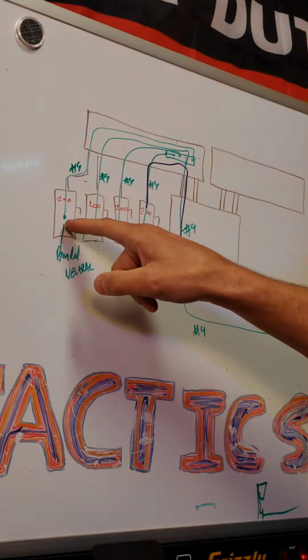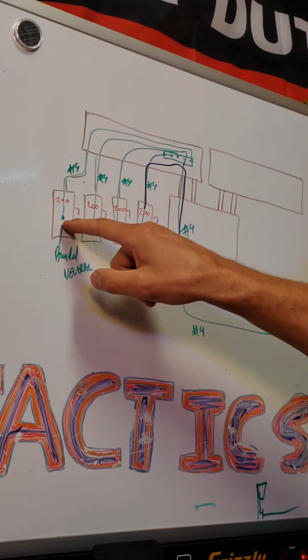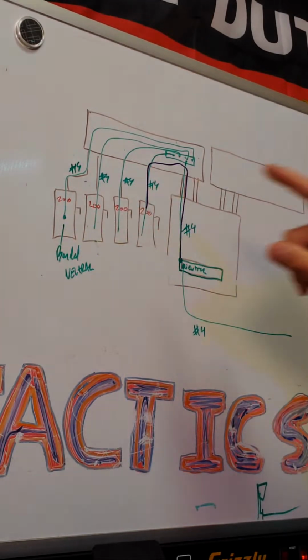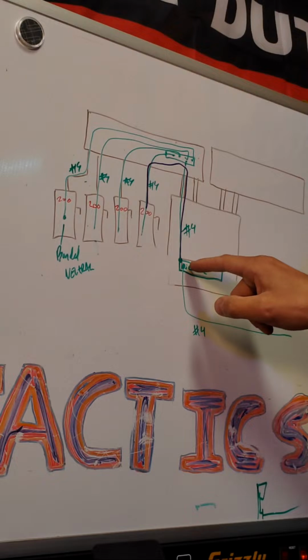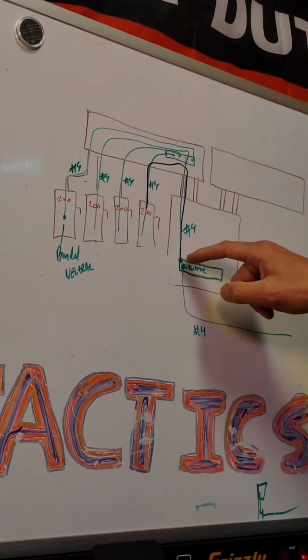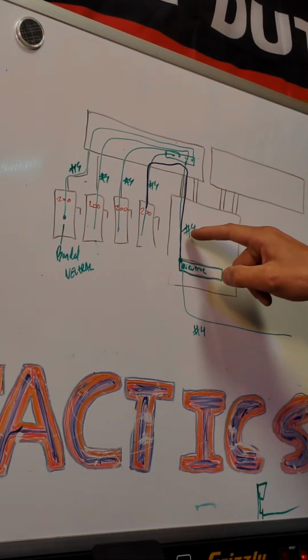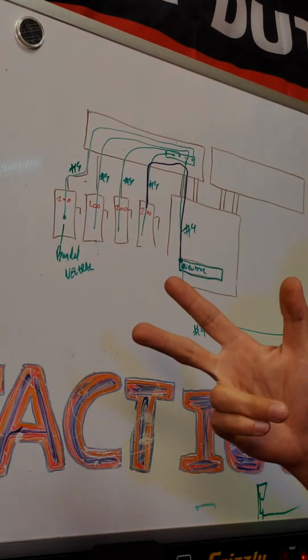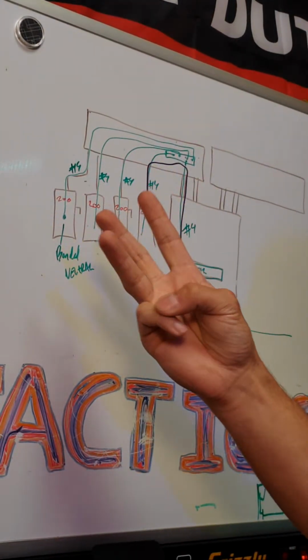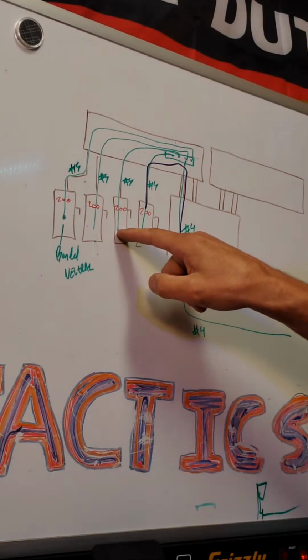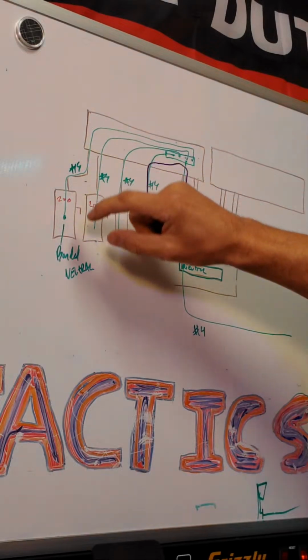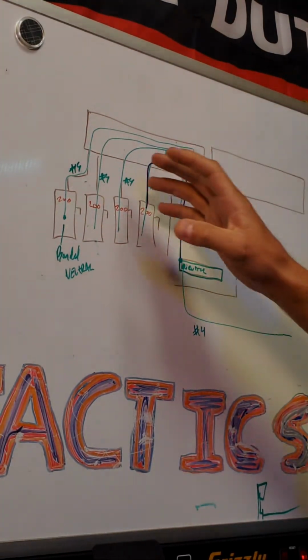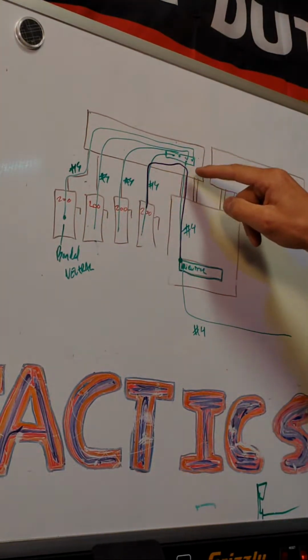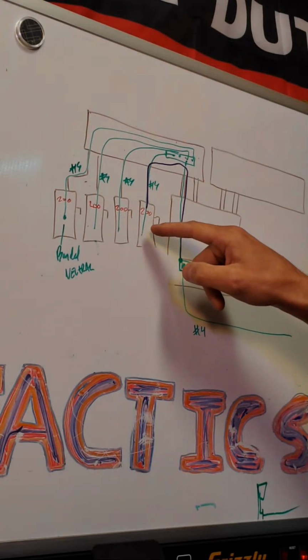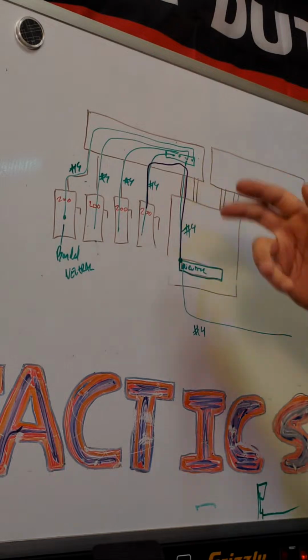But when you install this like this, when you bond your grounds at your sub panel or at your service disconnect, and you bond your grounds and neutrals at the source, a number 4 ain't going to cut it, because this is now a neutral, because you have just increased current by a multiplier of 4. My fingers aren't working. Multiplier of, that's 3. What the hell's wrong with me? 4. Multiplier of 4. One panel there, one panel there, one there, one there. We're taking, and they're essentially neutrals because they bonded here and they bonded here. They created a parallel path. They've got number 4 only to support what a 2-aught should be for the neutral. What's your thoughts?